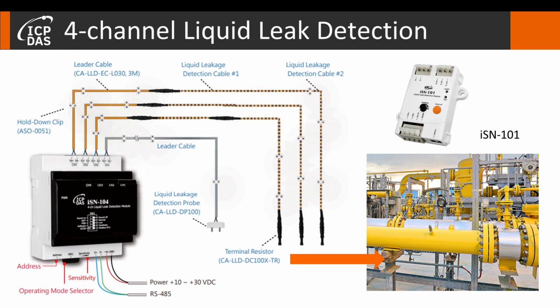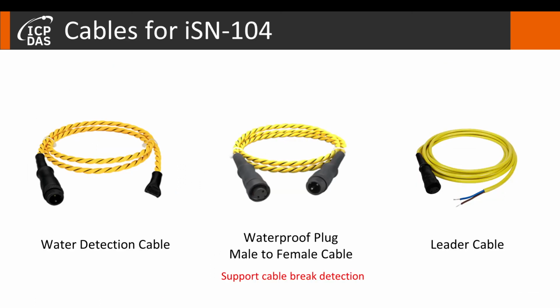Compared to our old water leakage detection module, ISN 101, the biggest difference is that ISN 104 has 4 channels instead of 1 channel. The 4 channels can connect with 4 sensors, and each sensor can be placed in different areas. The 4 channels with 4 sensors design can be used to replace the expensive addressable sensors. We have 3 different cables for our ISN 104. Water detection cable, waterproof plug male to female cable, and leader cable. Water detection cable is a sensor which can detect water leakage and is connected in the end part.